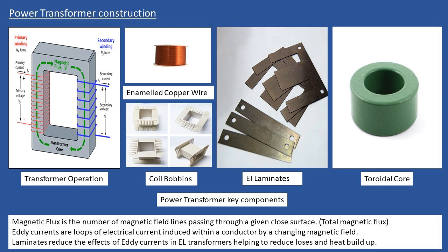So these laminates are then bolted together, and during manufacture, because you would have air gaps in between each one of them, commonly they are soaked in shellac, a varnish, normally in a vacuum type environment, to ensure that there are no gaps. And that shellac is then used to prevent these EI laminates from moving.